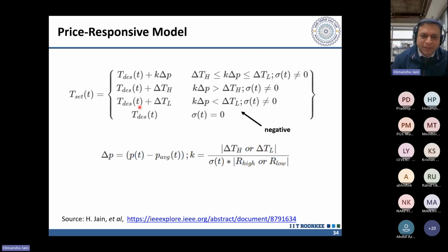Here, the price responsive behavior was very straightforward. You had a desired temperature that you would modulate based on the price differential in the last 2 time points, and a historical average represented by the standard deviation of the last 12 hours' prices. So how much I would want to change my desired temperature would depend not only on the current price differential, but also what was happening over the last 12 hours or so. And there was a maximum limit of delta TH and a lower limit of delta TL that I would change my temperature by.